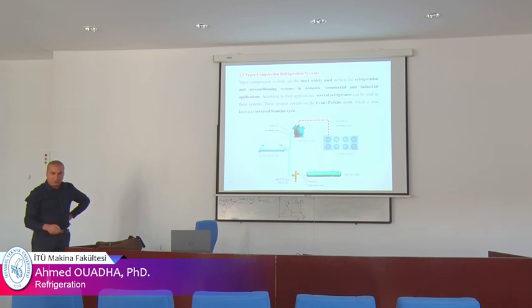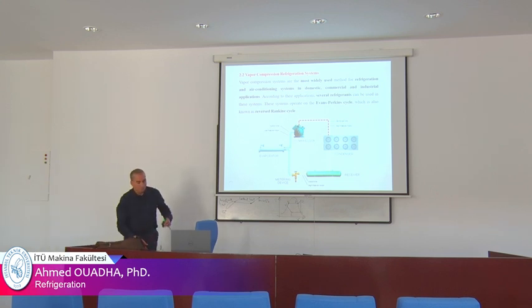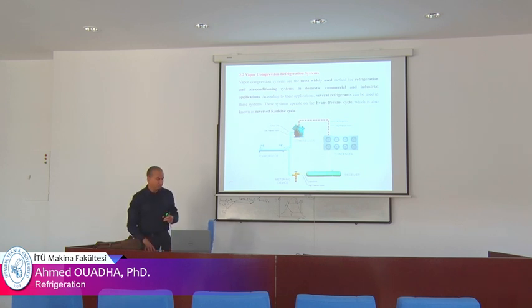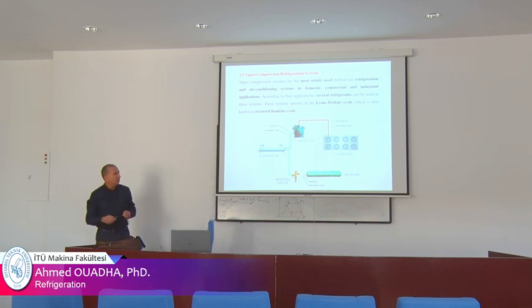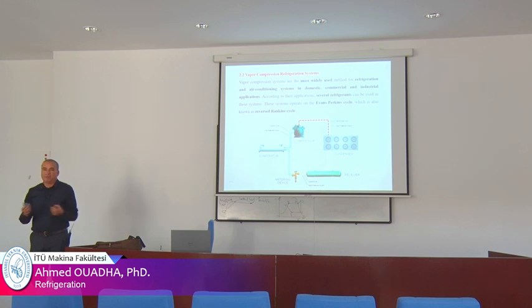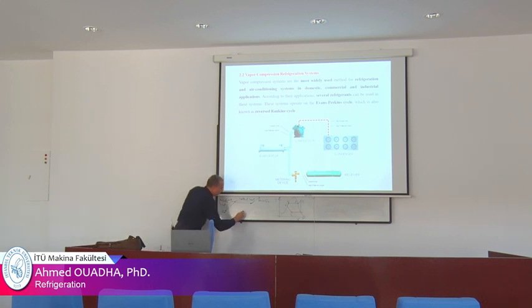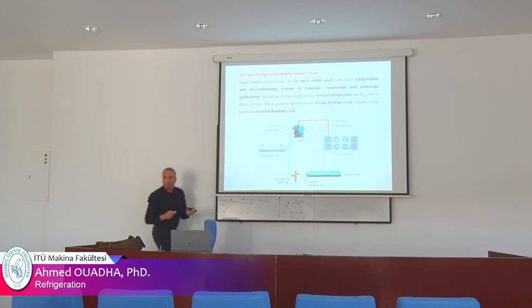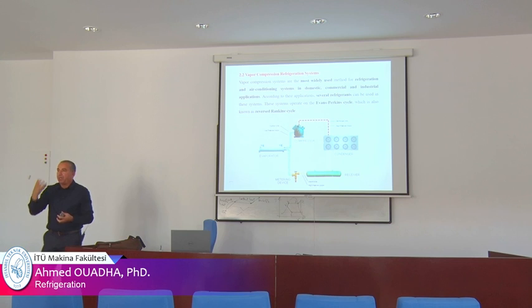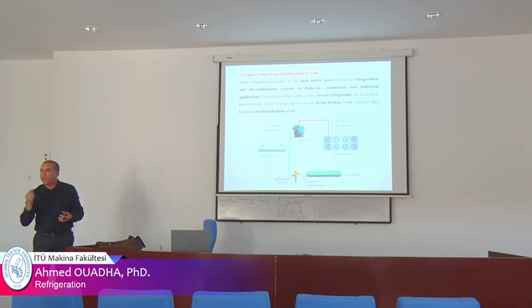Where? Like the metering device? The metering device. No, I haven't prepared it. No, I can't find it here. We can. A metering device is just a valve. In the refrigerant circuit we need that throttling to decrease the pressure from the condensation pressure to the evaporation pressure. Or, in the domestic refrigerator, we use a capillary tube. At the back of the refrigerator, there is a small tube, a tube with a small diameter. It's a capillary tube used here as a metering device.